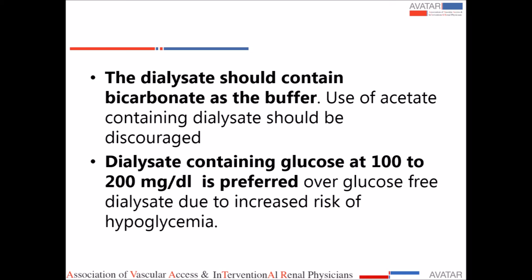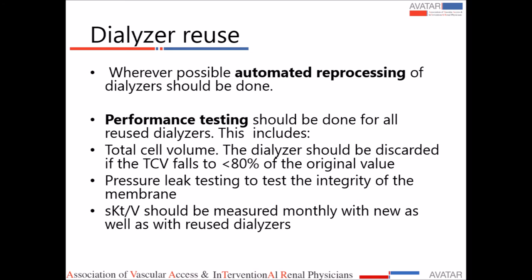Coming to dialysis membranes — biocompatible synthetic or modified cellulose membranes should be preferred over unmodified cellulose membranes. Bicarbonate should always be used as the buffer; use of acetate-containing solutions is to be discouraged. Dialysate containing glucose is preferred over glucose-free dialysate, as the latter increases the risk of hypoglycemia. If reusing the dialyzer, automatic reprocessing should be done followed by performance testing for all reused dialyzers. The total cell volume should be more than 80%; if it falls below 80%, the dialyzer should be discarded. Pressure testing should be done to test the integrity of the membrane, and KT/V should be calculated monthly for new as well as reused dialyzers.